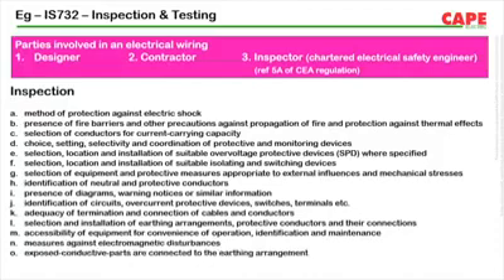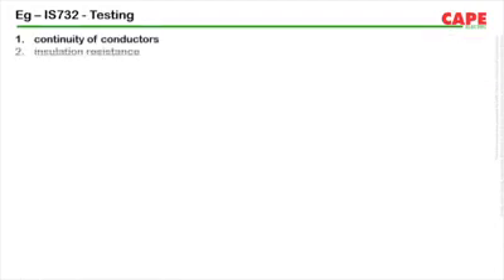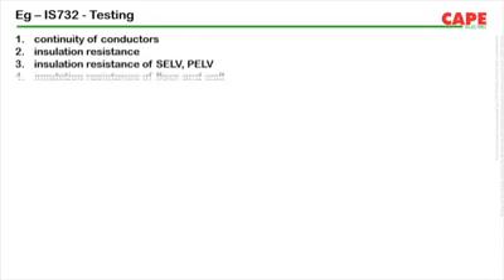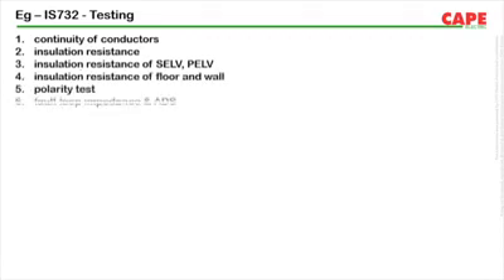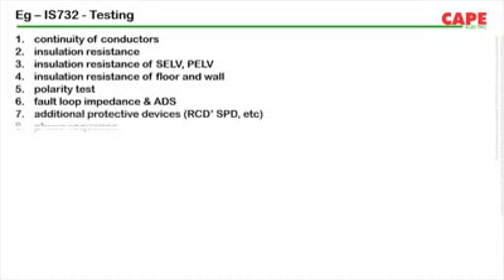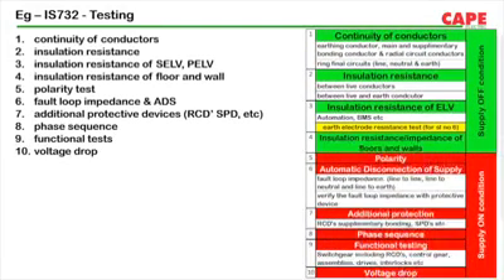Look at the list of inspection he has to follow. Look at the list of testing which he has to follow. The test shall follow the sequence. It's not just insulation resistance or earth electrode resistance and few danger boards, but a comprehensive list of testing which shall be made in supply off condition and supply on condition. If a test is failed, the inspector is supposed to inform the other two parties involved, meaning the designer and the contractor. Let them rectify the problem and start the test from the previous test in this list and continue the balance test in the same sequence.